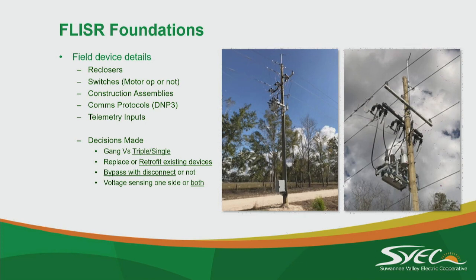One of the last decisions you need to think about is whether you're going to replace or retrofit your devices, and what your switching scheme will be outside of FLISR. These are reclosers - they're going to interrupt faults and change your coordination on your system. Also, will you need voltage sensing on one or both sides? That may change the relay or even the device you buy.